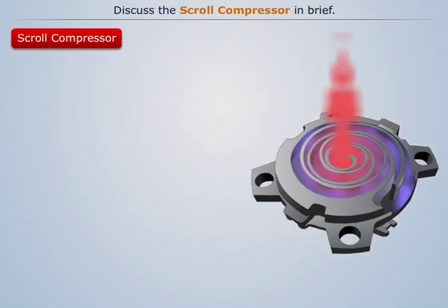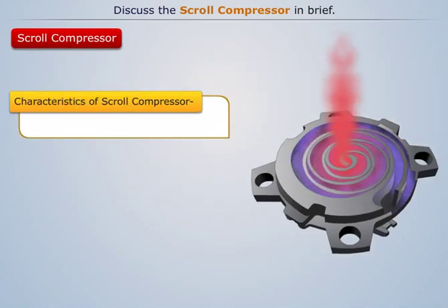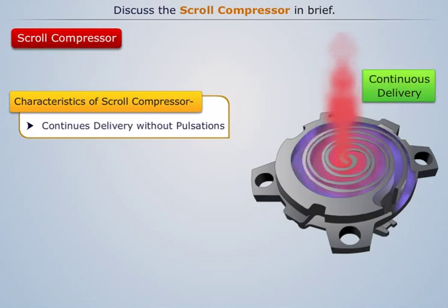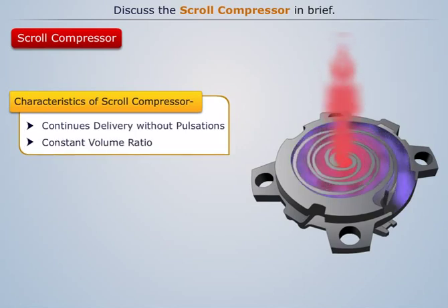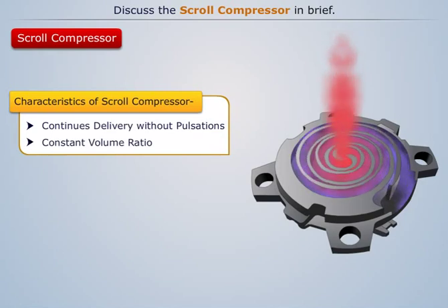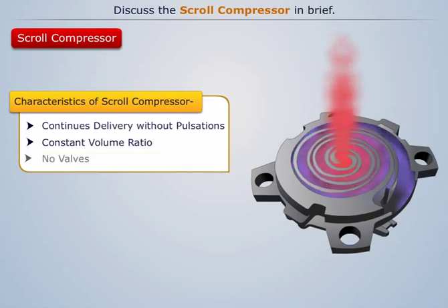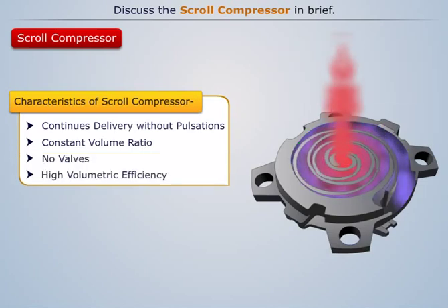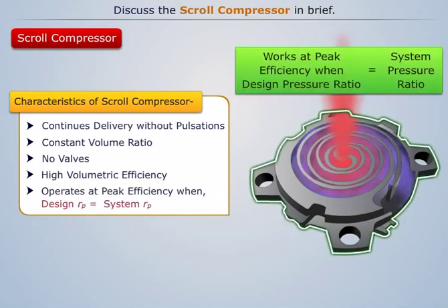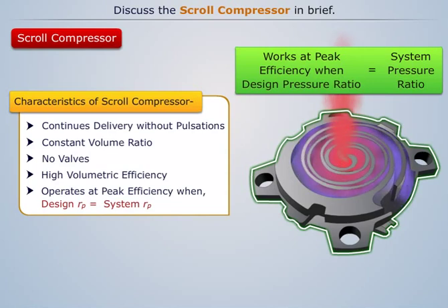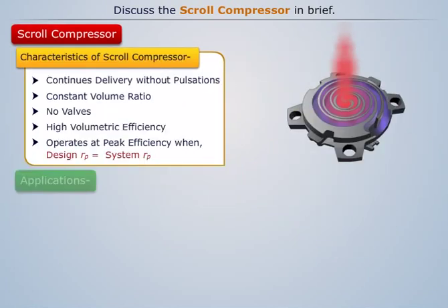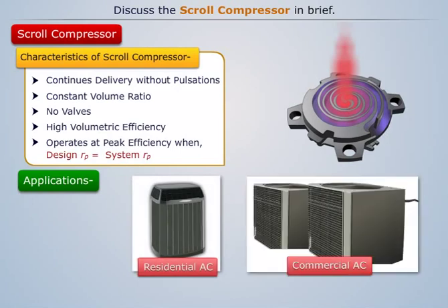The flow through this compressor is continuous with least pulsations. It is a constant volume ratio compressor, which is decided by the geometry of the scrolls and the location of the discharge port. It has no valves and has high volumetric efficiency. Scroll compressors operate at peak energy efficiency when the system pressure ratio equals the design pressure ratio. They are currently preferred in residential, commercial refrigeration, and automotive air conditioning, with capacity ranging from 1 TR to 14 TR.